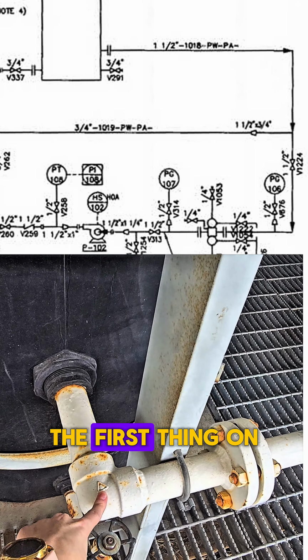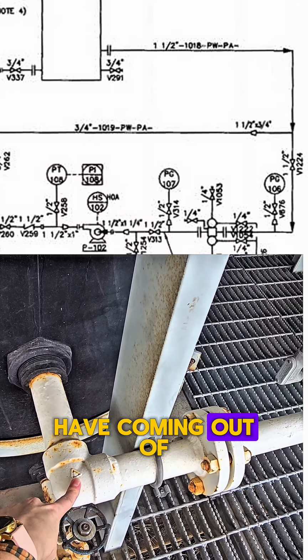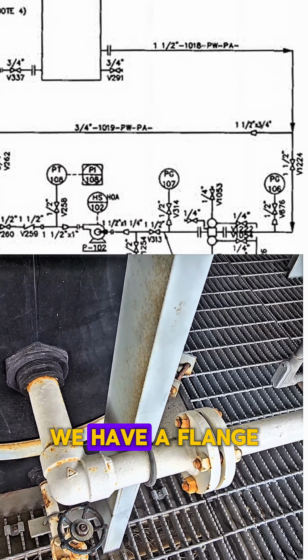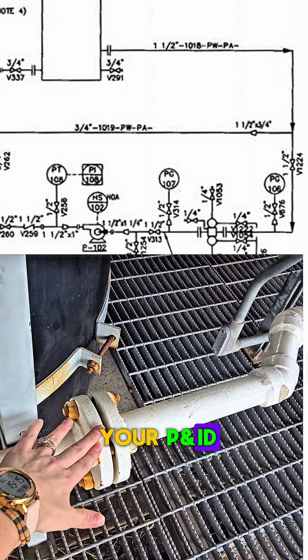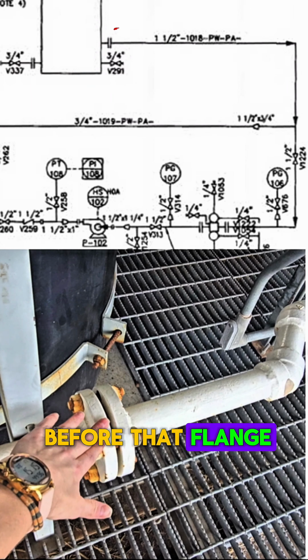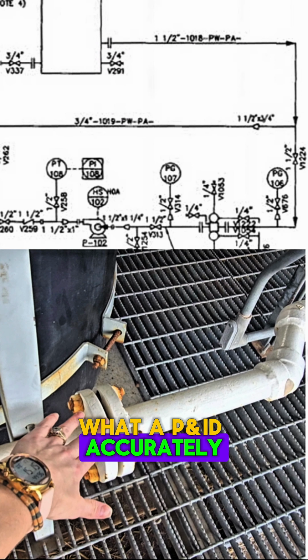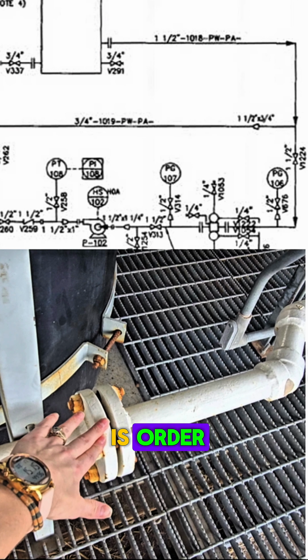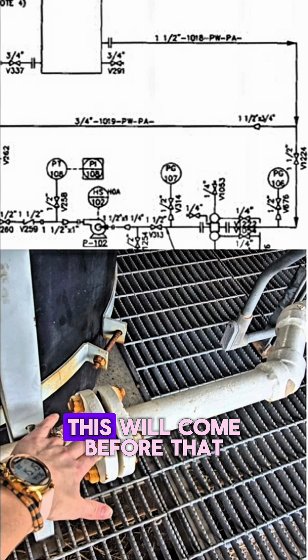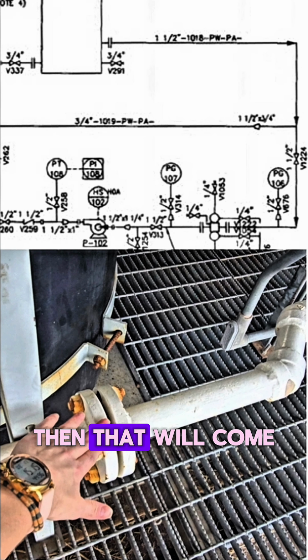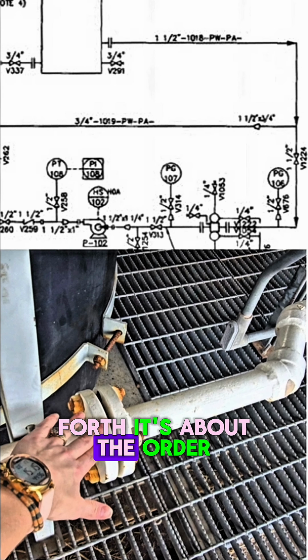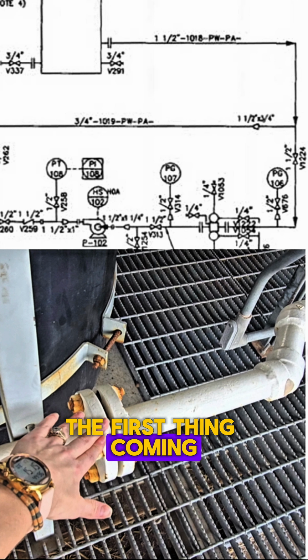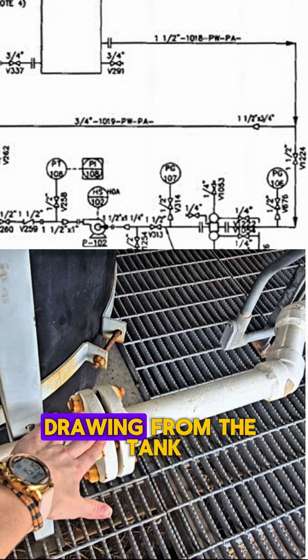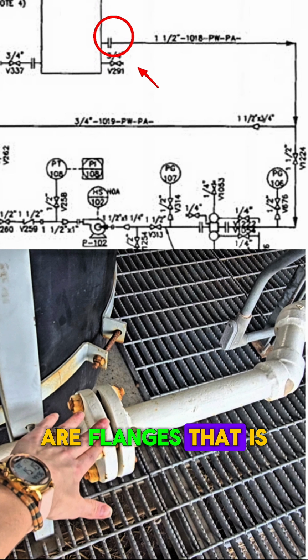For example, the first thing on the white line we have coming out of our tank is a 90, and then we have a flange. If you look at your P&ID, there's no 90 before that flange. What a P&ID accurately displays in the field is order. What that means is this will come before that, and then that will come before this, and so forth and so forth. It's about the order. The first thing coming out on our P&ID drawing from the tank are flanges. That is the first thing we have in the field.